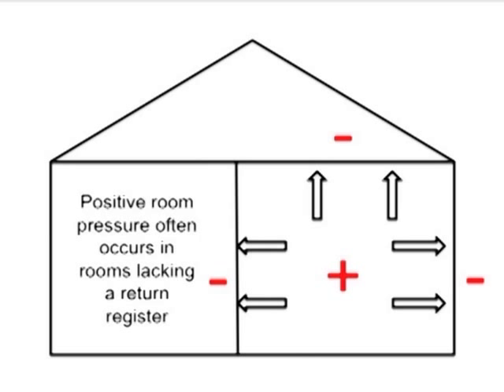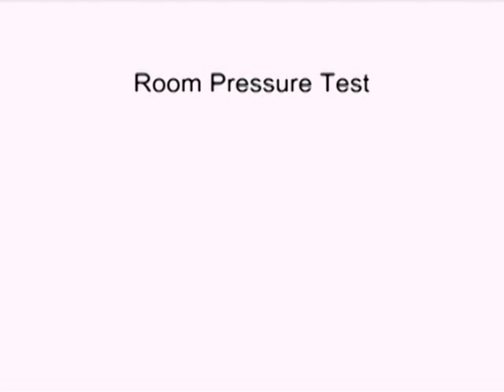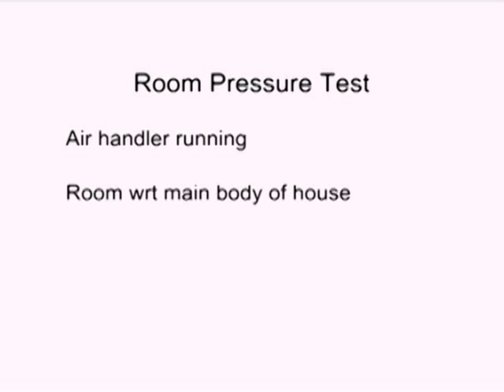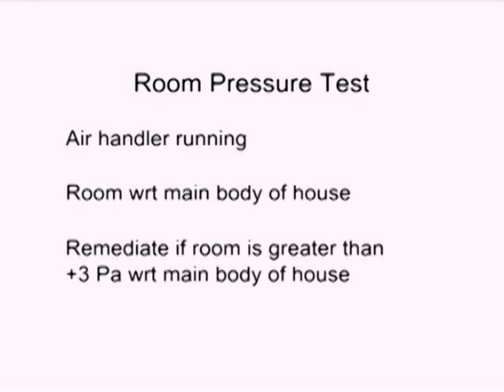Excessive room pressure is often caused by the absence of a room return register in homes with forced air systems. Testing rooms for positive pressure is easy and is done with the air handler running. Test the room pressure with reference to the main body of the house. A positive pressure equal to or greater than 3 pascals requires remediation.